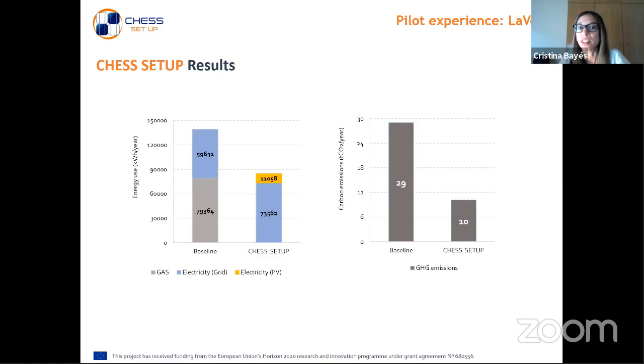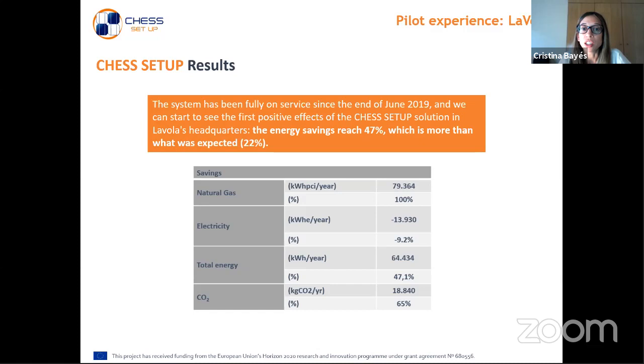So we avoid the consumption of the existing chiller, but we have the new heat pump. Summarizing, to finish the presentation, the total energy savings is 64,000 kilowatt hours per year, that is a 47% saving compared to the baseline. Savings in greenhouse gas emissions are close to 19 tons of CO2, a reduction of 65% of the total emissions of the building compared to the baseline situation. This also represents an estimated energy cost saving of 2,700 euros per year for the building.